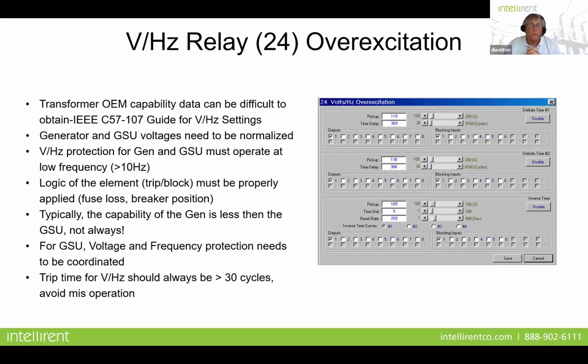For transformer protection for volts per hertz, there was a new IEEE guideline. In fact, I was secretary on this working group, because the old volts per hertz curves were back in the 50s and done by GE, and they haven't been looked at ever since. What we found was that the new designs on some of the newer transformers had a much higher thermal capability and thermal rating than some of your older transformers. So the curves have been updated in C57.107, and that's a good guide to help you put this setting in properly. But typically the capability of the generator is less than that of the GSU, but not always. It depends on the age and the type of transformer that you have.